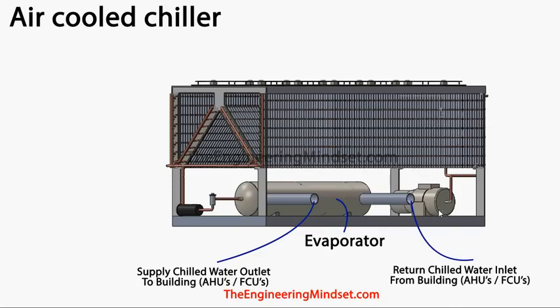So we've got one entrance which is coming in, and that's coming from the buildings and the AHUs and the fan coil units, and it makes its way through there. We'll have a look inside this one shortly as well, and it will then make its way back out around the buildings, the AHUs and the fan coil units, to provide that cooling. And the water will usually flow in the opposite direction to the flow of refrigerant, and that's where you get your maximum heat transfer and your LMTD, or log mean temperature difference. So when the refrigerant has now left the expansion valve, it will be a low pressure, low temperature liquid vapor mixture, and it will then pass through the evaporator and absorb all the unwanted heat that's come back from the building.